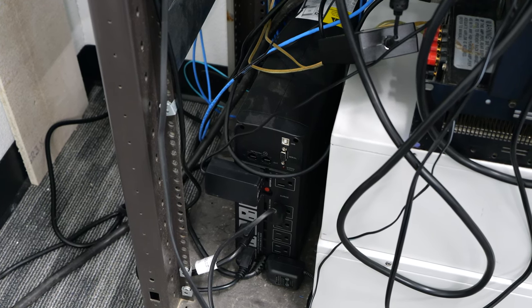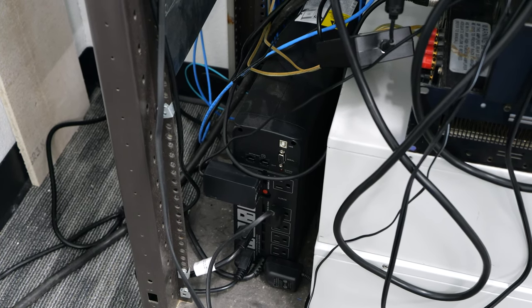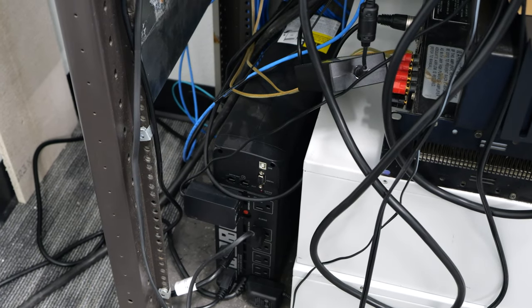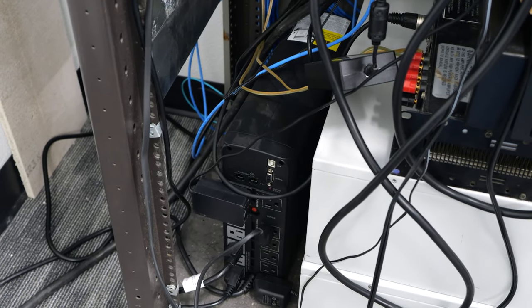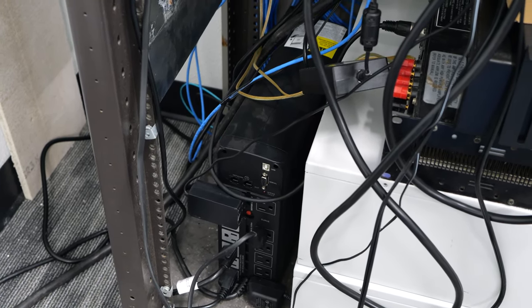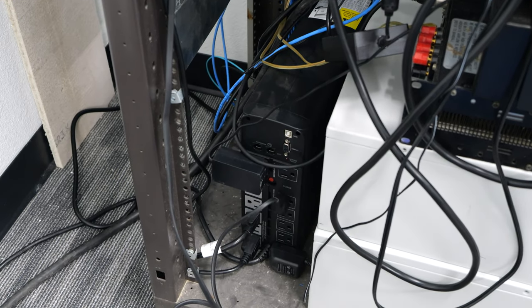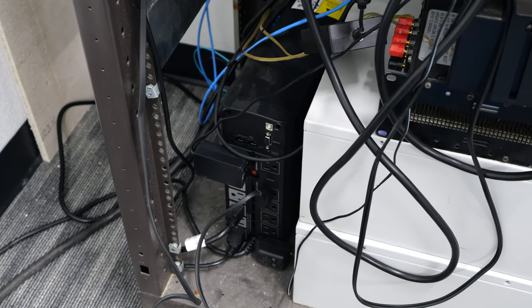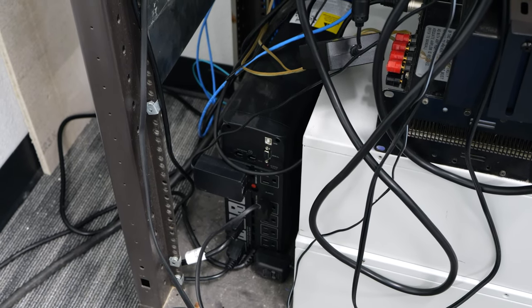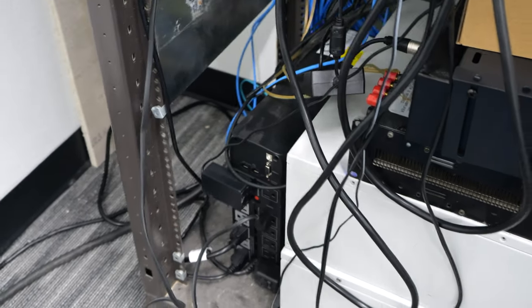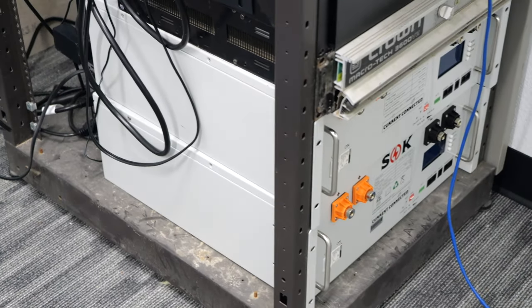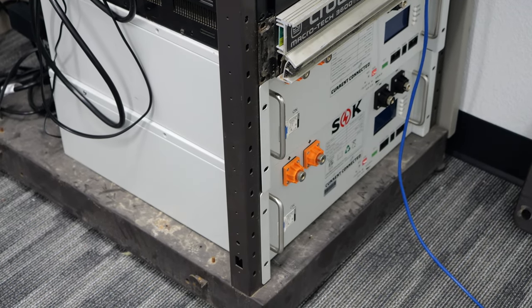For the time being, we have a little tiny APC UPS, and it really struggles because this rack idles at about 700 watts of load. As we add more stuff, this thing is just going to become completely overwhelmed. It currently gives us about eight minutes of backup runtime, and we're going to dramatically increase this by adding the 10 kilowatt hours of lithium iron phosphate storage.